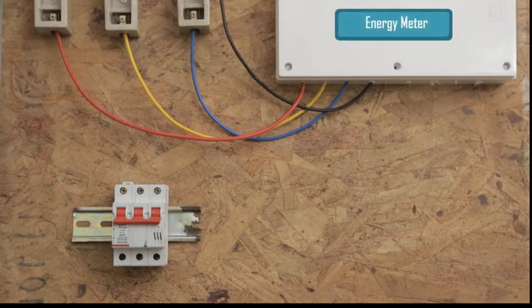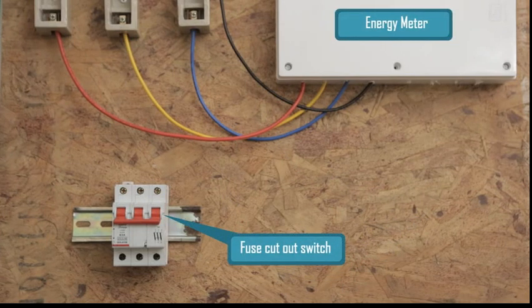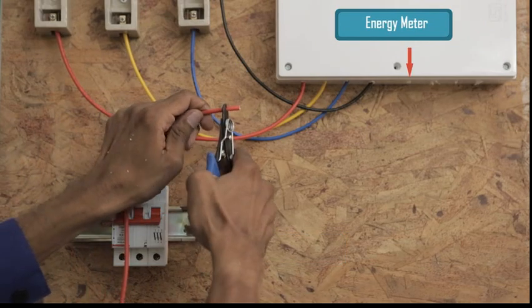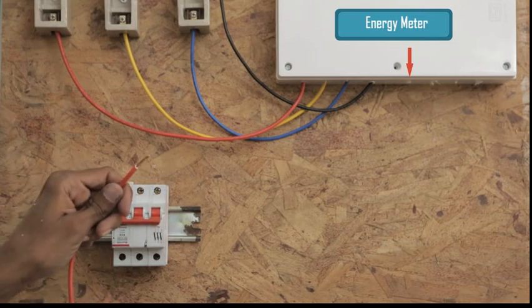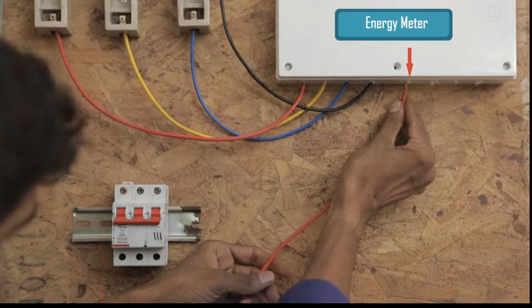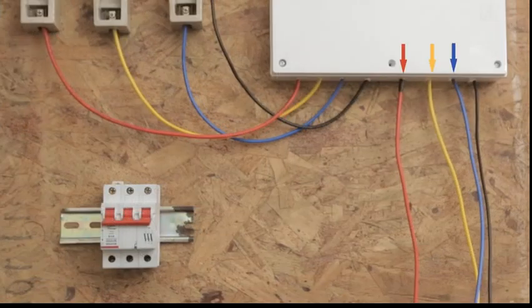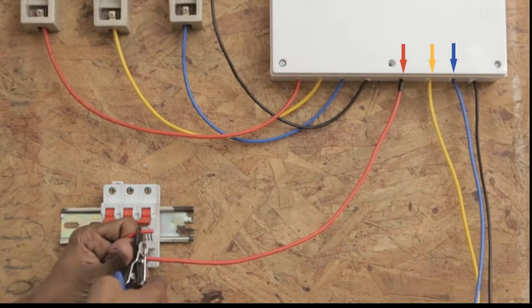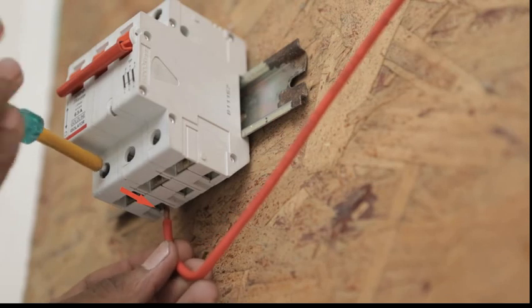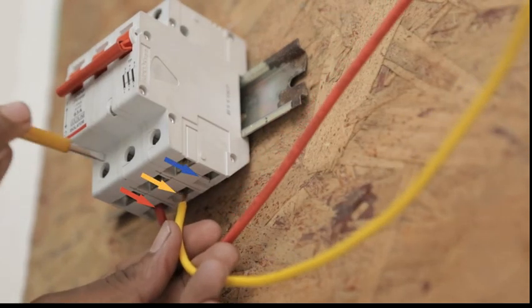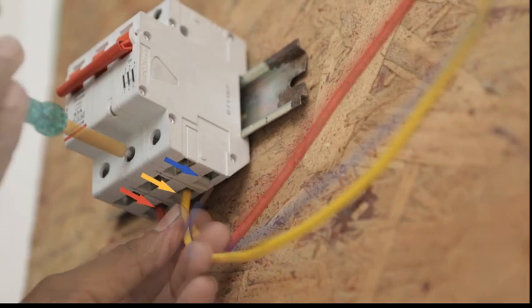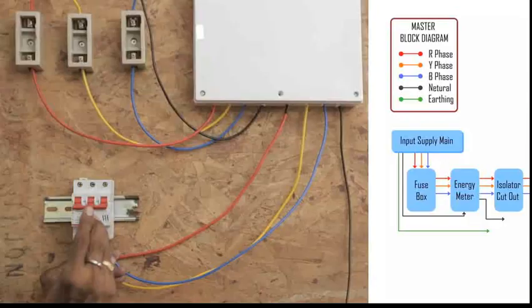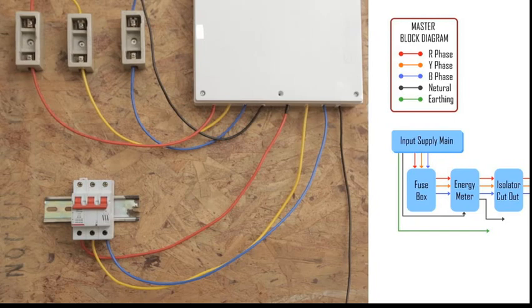Finally, we connect the energy meter to the fuse cutout switch. Start by inserting the red wire into the R phase output of the energy meter. Then insert the yellow and the blue wires into the Y and B phase output terminals of the energy meter. Then connect the R output of the energy meter to the R input of the fuse cutout switch. Similarly, connect the Y and B outputs of the energy meter to the Y and B inputs of the fuse cutout switch. Close the fuse box.